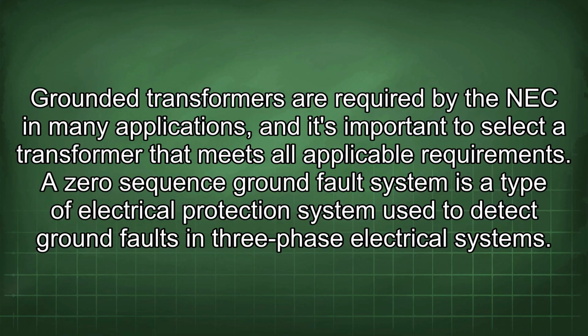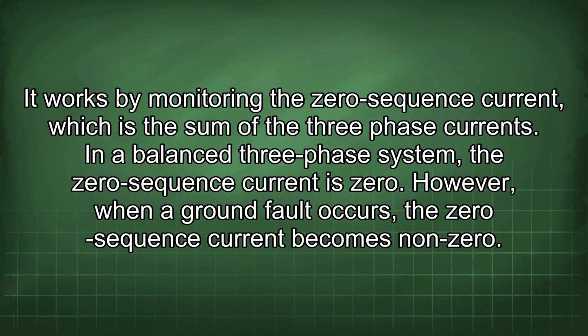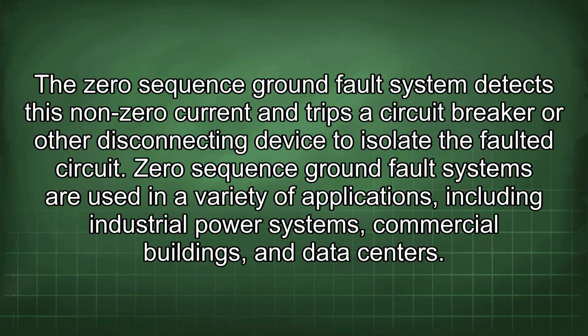A zero-sequence ground fault system is a type of electrical protection system used to detect ground faults in three-phase electrical systems. It works by monitoring the zero-sequence current, which is the sum of the three-phase currents. In a balanced three-phase system, the zero-sequence current is zero. However, when a ground fault occurs, the zero-sequence current becomes non-zero.